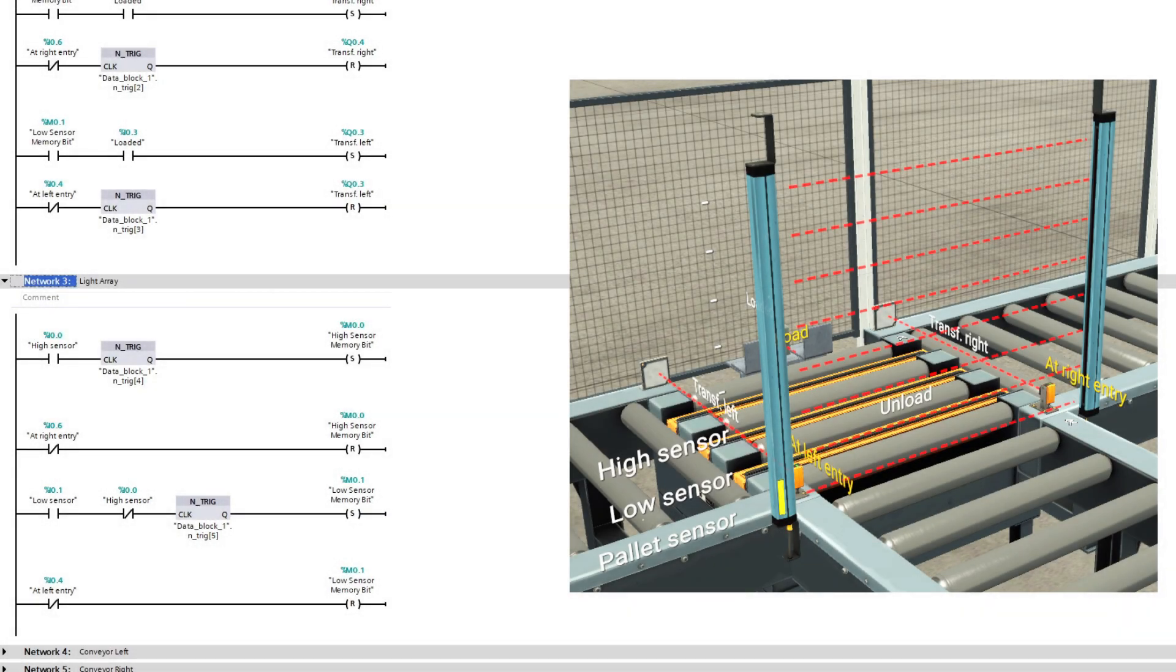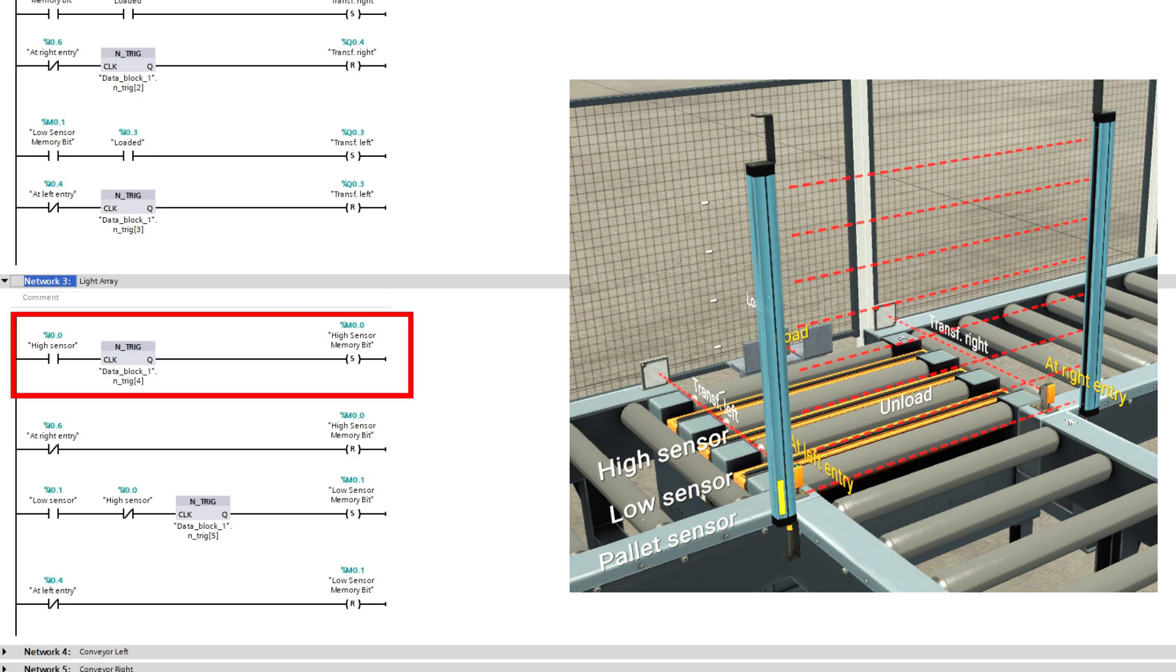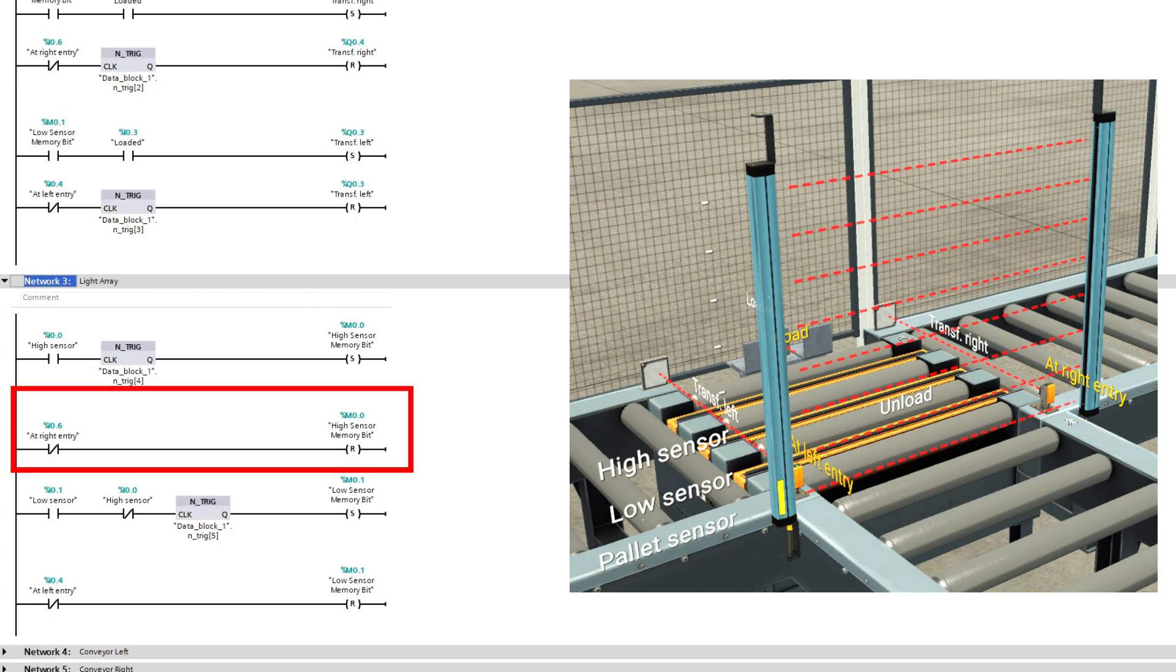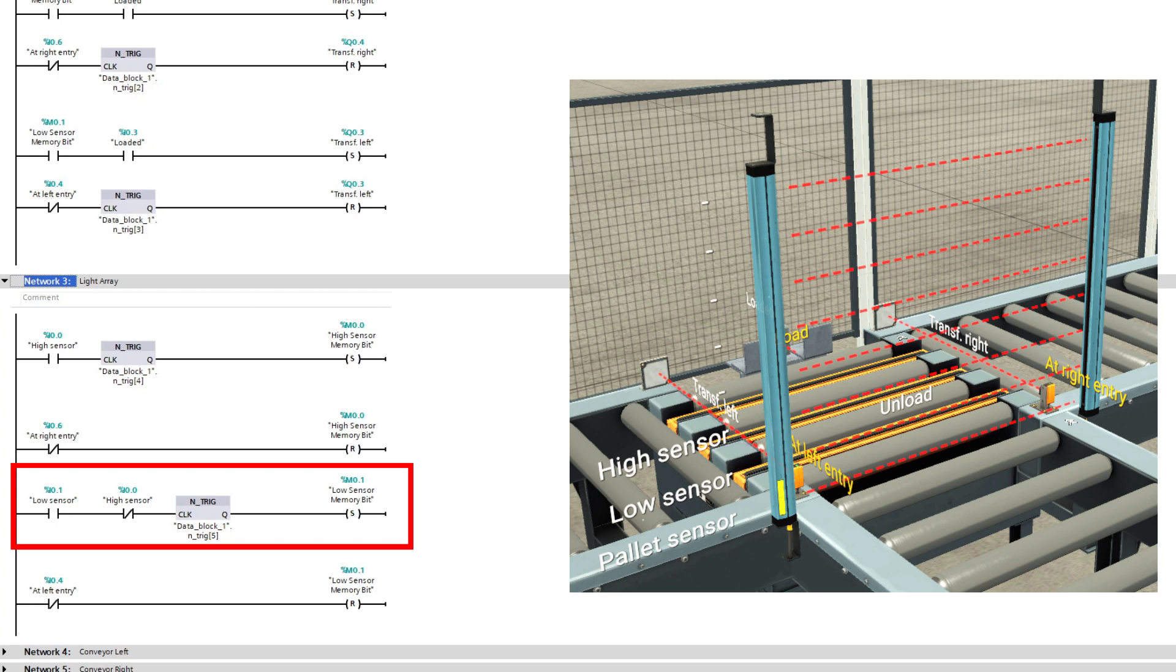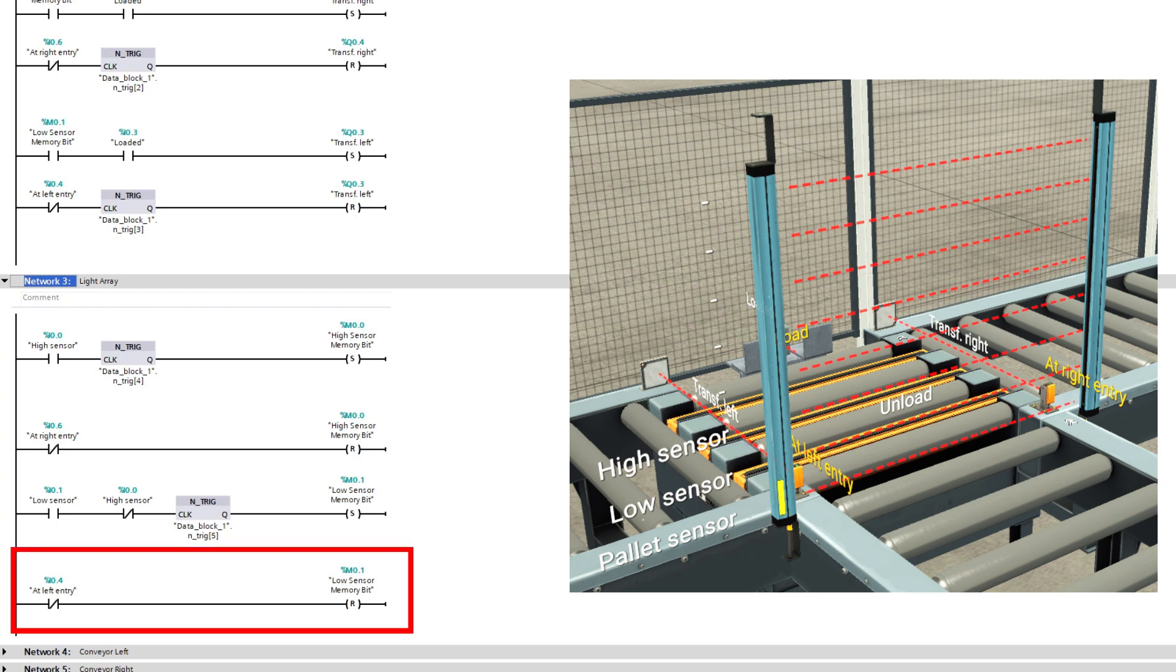The light barrier will keep track if it's a small or big box on the pallet. If it is a big box, the high sensor will set the high sensor memory bit I made, and it will get reset once the at right entry sensor gets occupied. And for the pallets with small boxes, it's the same thing, just that we need the lower sensor and not the higher sensor to set the memory bit. And then it's the at left entry sensor that will reset the bit.